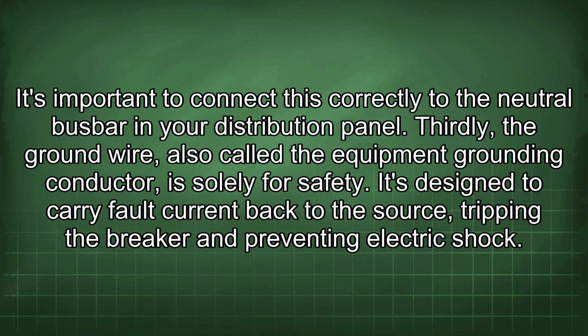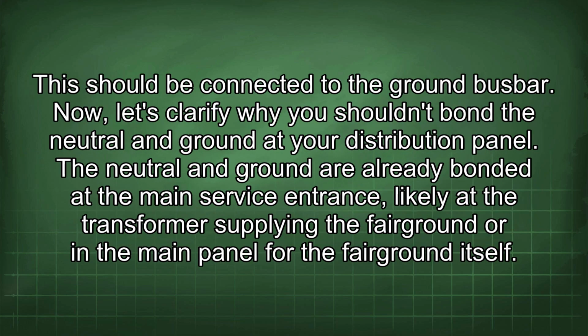Thirdly, the ground wire, also called the equipment grounding conductor, is solely for safety. It's designed to carry fault current back to the source, tripping the breaker and preventing electric shock. This should be connected to the ground busbar. Now let's clarify why you shouldn't bond the neutral and ground at your distribution panel. The neutral and ground are already bonded at the main service entrance, likely at the transformer supplying the Fairground or in the main panel for the Fairground itself.